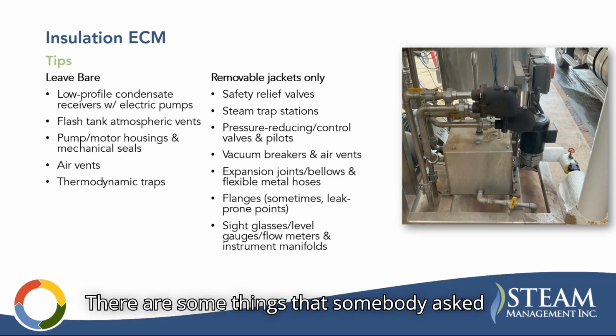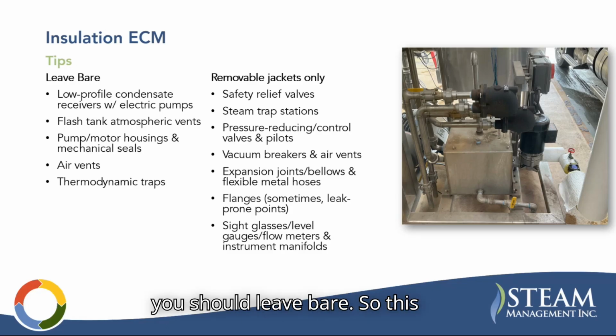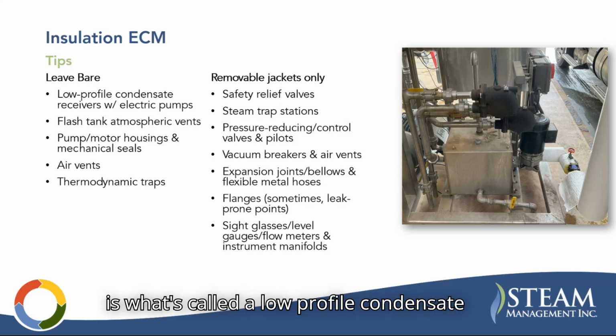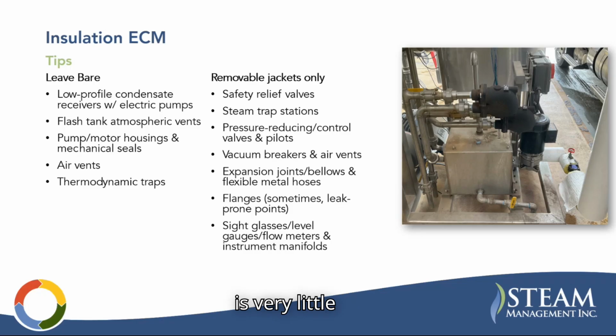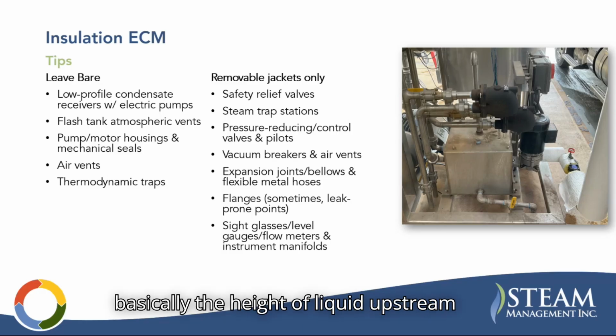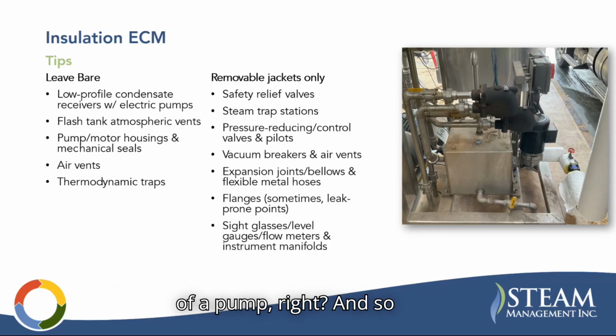There are some things. Somebody asked earlier, so there are some things that you should leave bare. This is what's called a low profile condensate receiver with electric pumps. You see, this is a short tank with a pump mounted on the side of it. There is very little NPSH available, net positive suction head available, which is basically the height of liquid upstream of a pump, right?